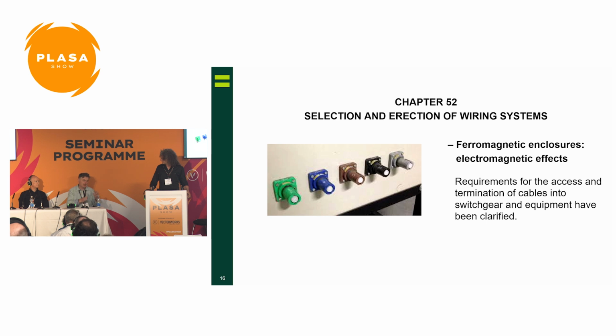You've got, pardon me, three lives, neutral and any leakage currents on the protective conductor, all completely balanced in that one panel. So I've never come across these things warming up in use or being an issue, and I'll be interested to know if anyone else has. But what's gone in here is deemed to be a bit of a relaxation. So it isn't all bad news, you see. We're making it easier for you out there.